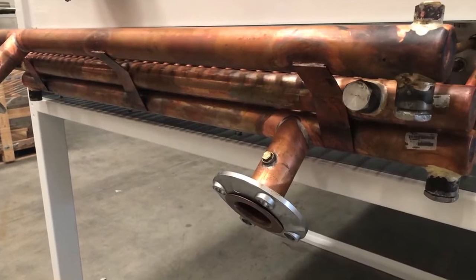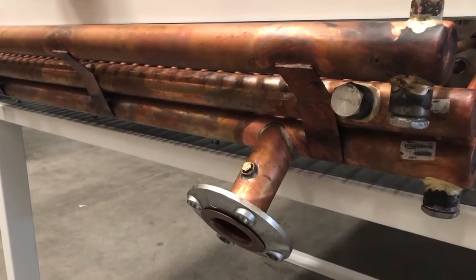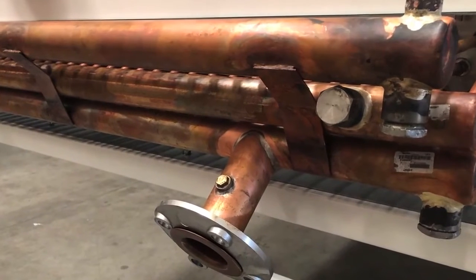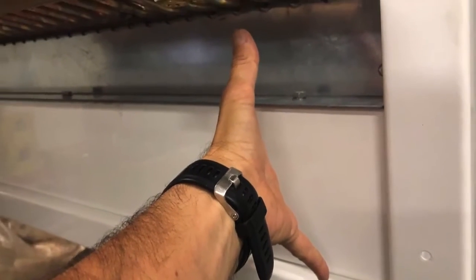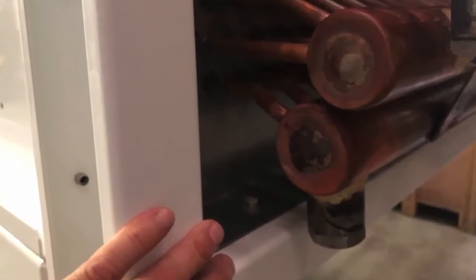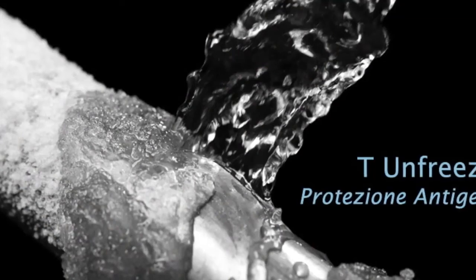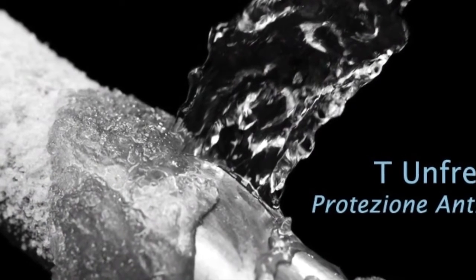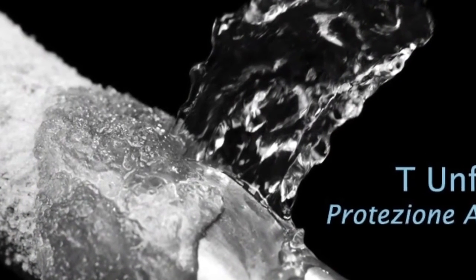When we go to stop the plant during the winter period for a few days break, for example, for holidays or a production pause of the plants, we will simply open some valves and completely drain the water inside the heat exchanger. In this manner, even in the event of frost, naturally the heat exchanger will not freeze and will not incur damage. As can be observed from the pictures, in order to accomplish this outcome, the exchange package is typically installed at an incline, and there exists a specific circulation that enables draining, that is, fully emptying the water inside the exchanger. In all other instances, a combination of water and antifreeze is utilized to completely prevent freezing.